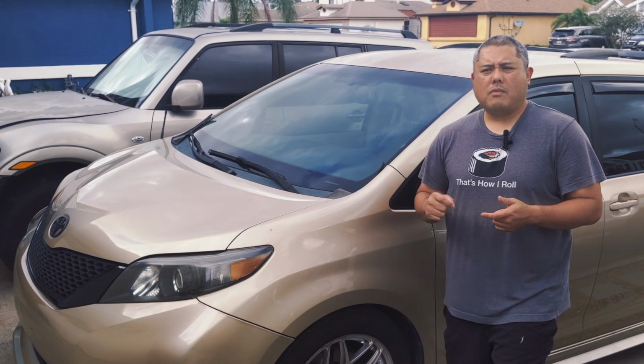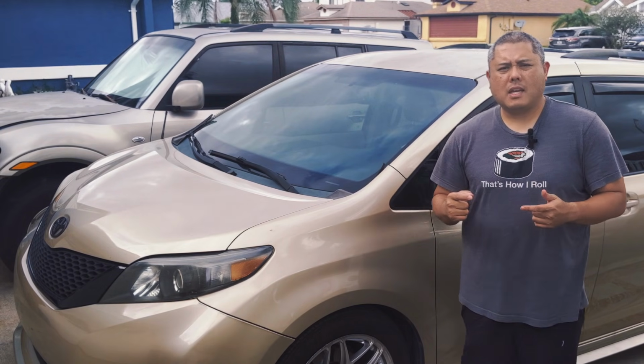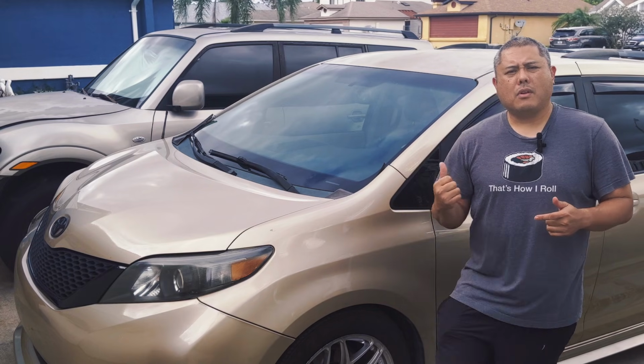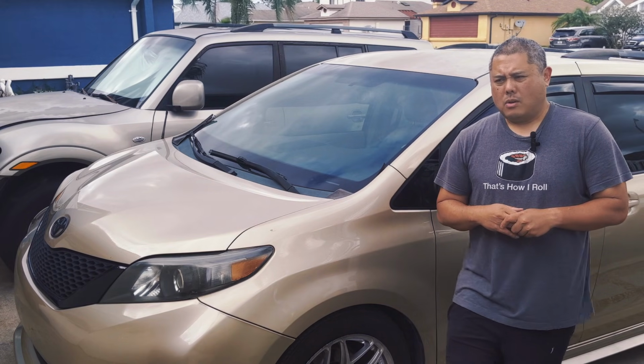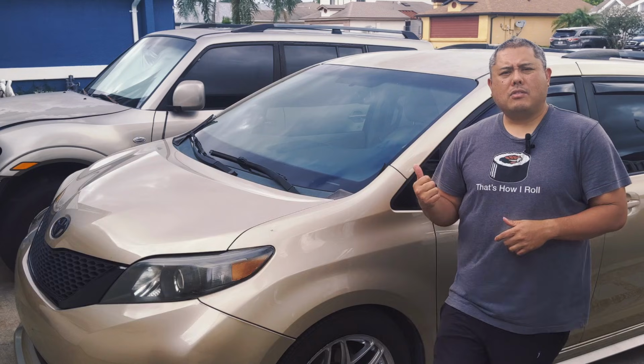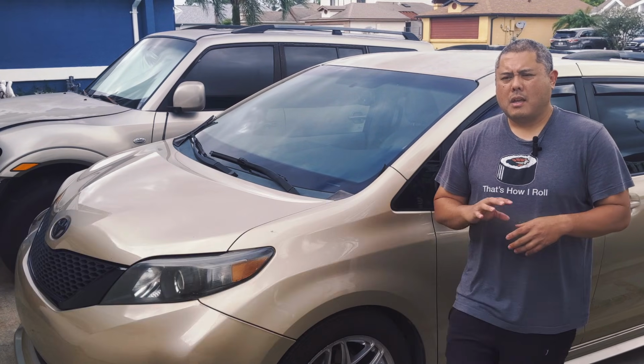I hooked it up, and from the readings on the gauge, it looked like I had a faulty expansion valve. So I went ahead and replaced the expansion valve, and after refilling the system, everything looked good.